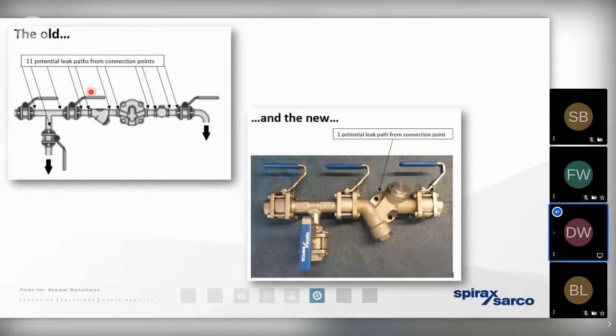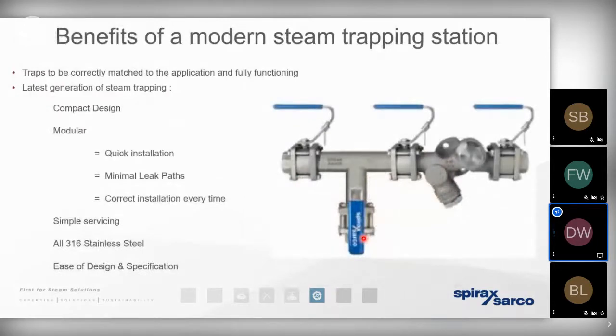So for that reason, certain steam trap types are available in what we call a modular pattern. That's essentially where all of the components that you can see up in the top left have been brought together in the same casting. So that brings us a number of different benefits. First of all, we've minimized those leak paths that could otherwise have existed. It's smaller in footprint, so it's easy to install and bracket together. It means that we've got less opportunity for an incorrect flow configuration or incorrect sequence of components. And it's also cost effective to now manufacture it out of a high grade stainless steel material.